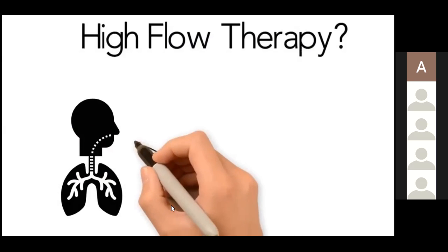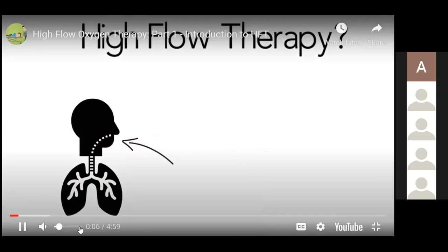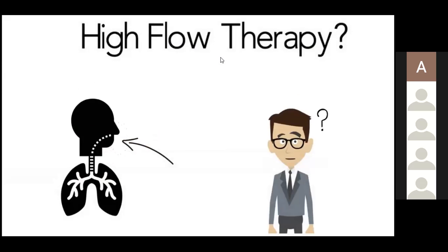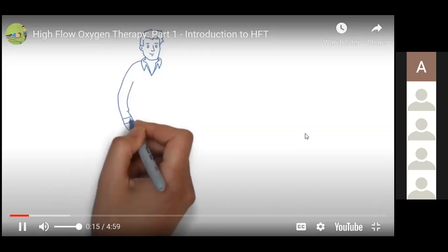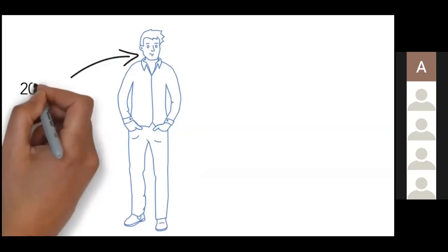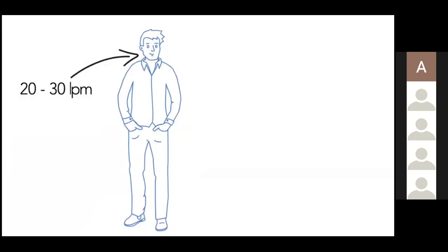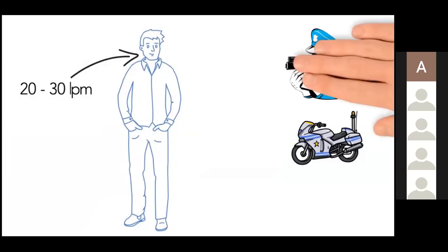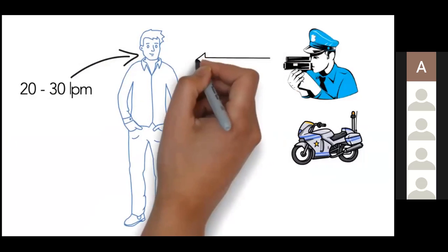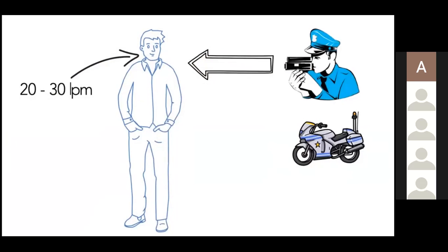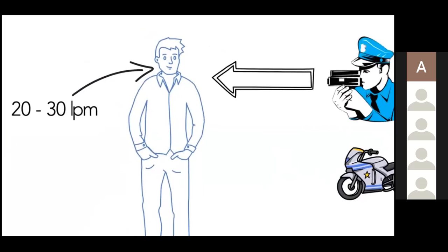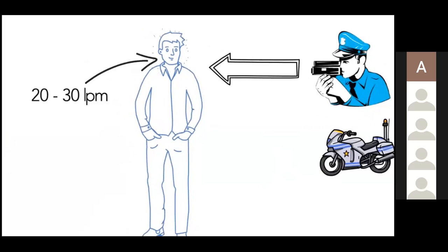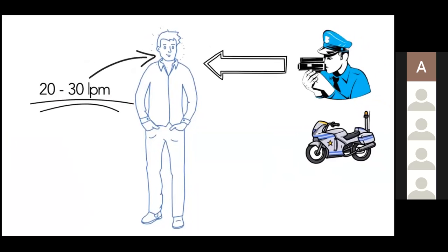High flow therapy. High flow therapy is when oxygen is being delivered to the patient at a flow rate that meets or exceeds their inspiratory flow demand. What does that mean? Well, did you know that at rest, the average adult will inhale at a speed of 20 to 30 liters per minute? In other words, if someone was standing next to you with a radar gun pointing at your nose, capable of measuring how fast you're inhaling while you're relaxed, the speed at which you inhale would be around 20 to 30 liters per minute. So high flow therapy should be capable of matching the inspiratory flow or even exceeding it.